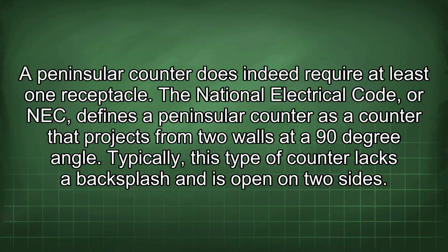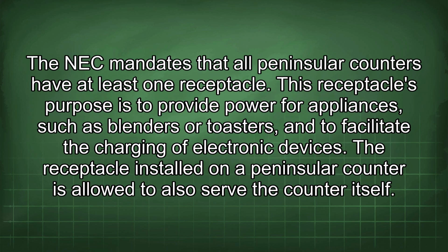A peninsular counter does indeed require at least one receptacle. The National Electrical Code, or NEC, defines a peninsular counter as a counter that projects from two walls at a 90-degree angle. Typically, this type of counter lacks a backsplash and is open on two sides. The NEC mandates that all peninsular counters have at least one receptacle.